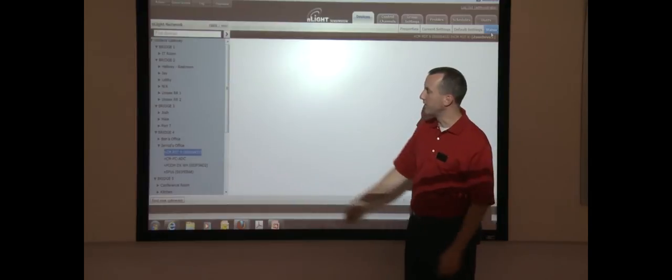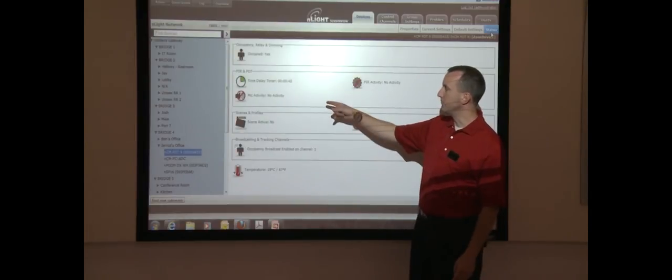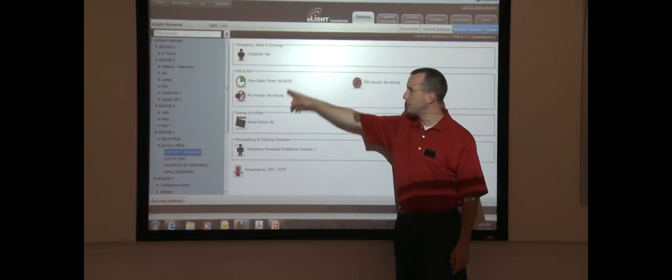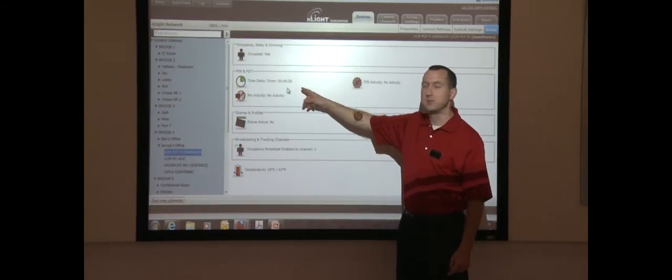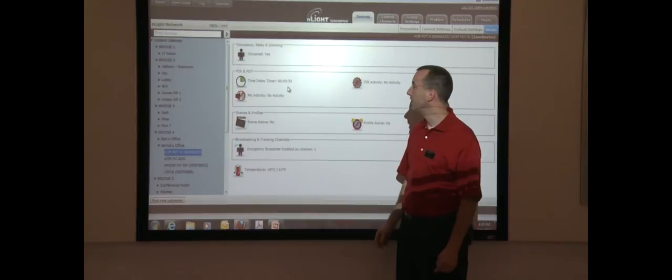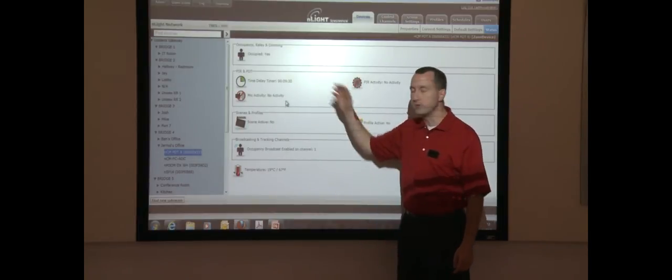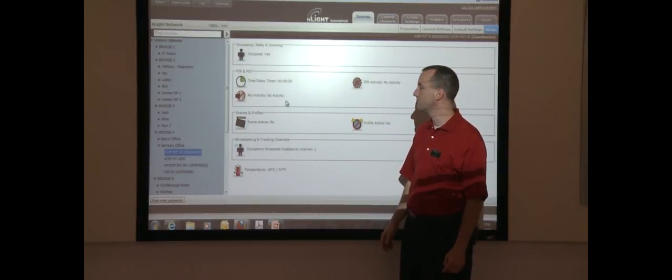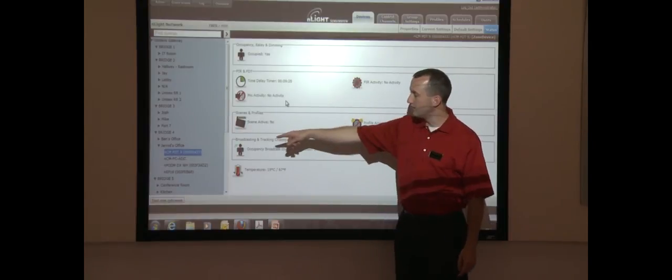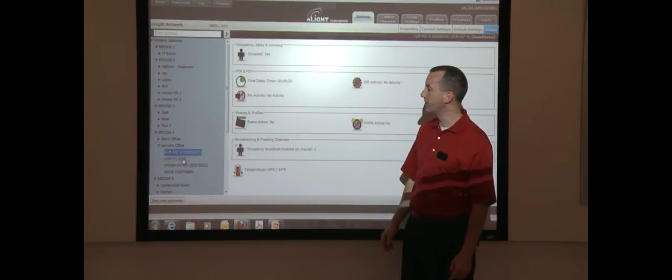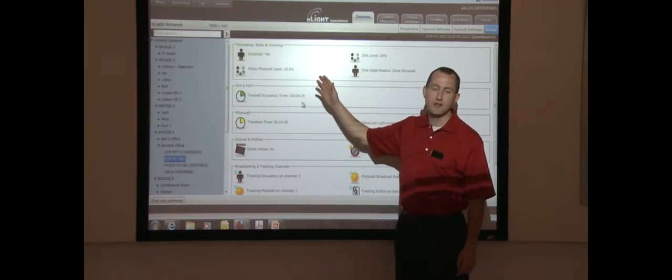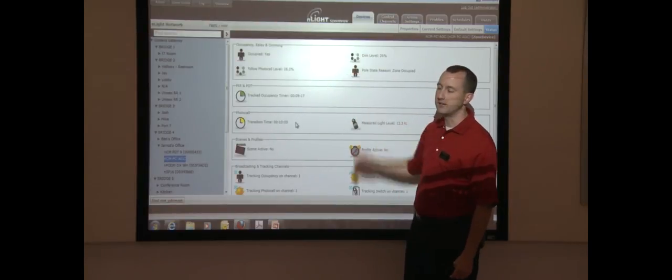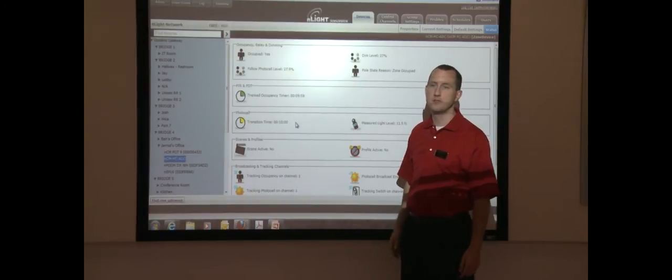If we go even deeper, we can look at status. In real time, we can see that in Jared's office here, he last moved 20 seconds ago because we see the actual PIR time delay counting down. If he was talking, we would see the microphonic icon twitch. If you go into a photo cell, you get even more information about what the current light level is, what the dim level of the device is. All this is tracked in real time.